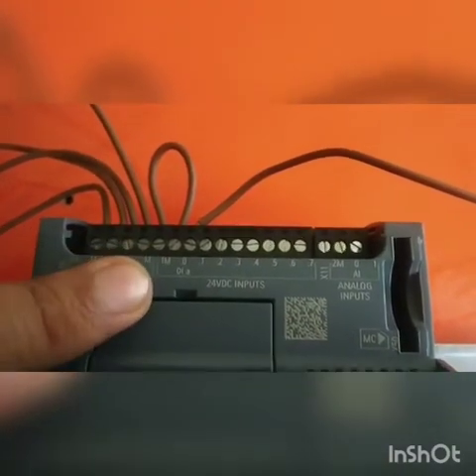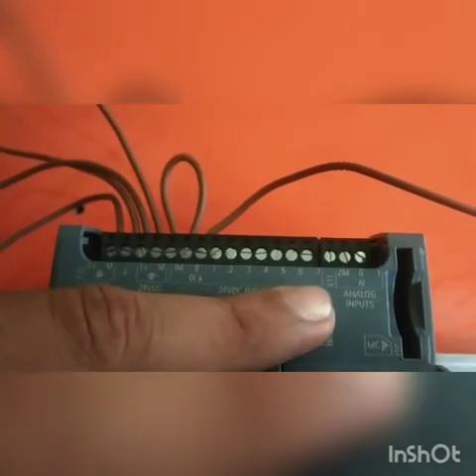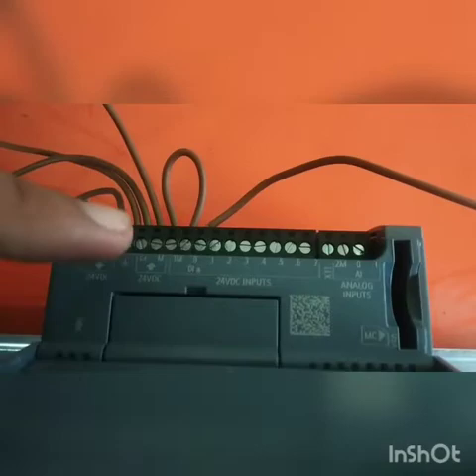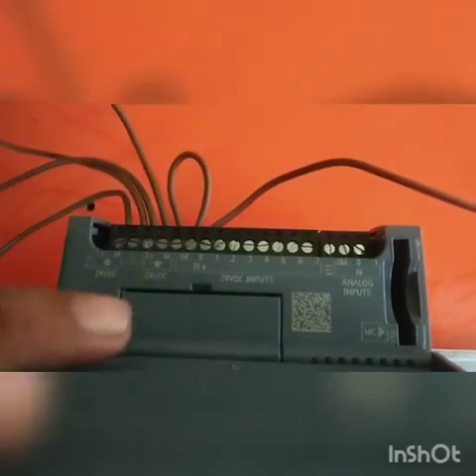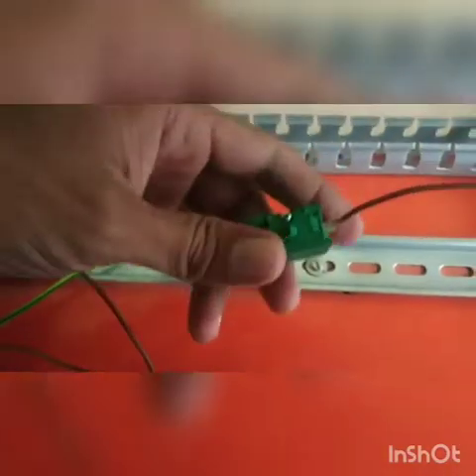This M is then connected in common with 1M. 1M is the input digital card, where there are 8 digital inputs. Also, 2M is the analog input card. This M, which is 0V, is connected to 2M and also 1M. So accordingly it will give 0V to both cards. Now we are connecting L-plus.